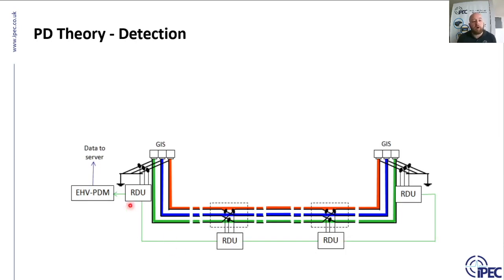Now, just a note on EHV. On extra high voltage circuits, along the circuit themselves, there are link boxes and cross-bonded joint locations. So what it means is we also have extra opportunities to install HFCT sensors. On top of that, EHV cables tend to be very long, and the typical range of a HFCT is about 4 or 5 kilometers. So on an EHV circuit that is maybe 15 or 20 kilometers, it's quite nice to be able to install HFCTs along the cable length.